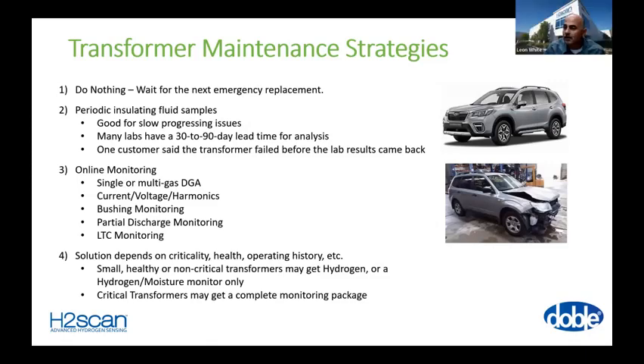Right. We were talking to somebody at a conference recently who said at least their labs are currently looking at 30 to 90 day lead times to get analysis back. This customer had some high industrial lighting loads that were generating lots of harmonics and failing like two MVA transformers after a couple of years. They said in some cases they've seen where last year's sample looked fine, they took an oil sample, and before the sample came back this year, the transformer had already failed.